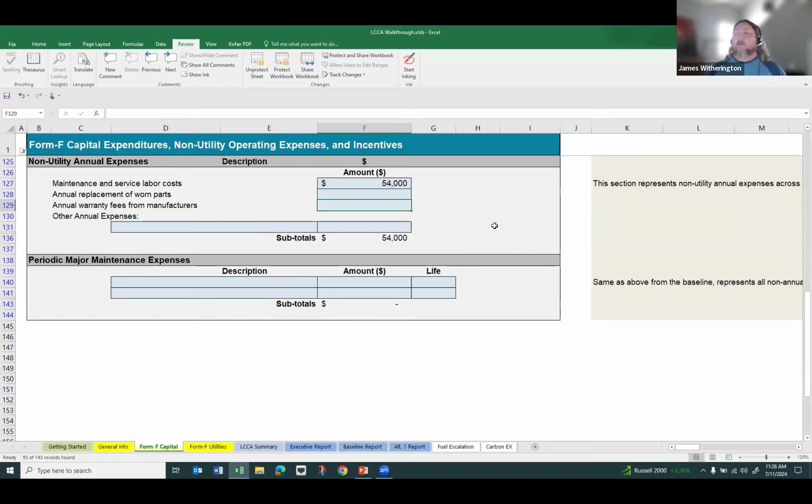What we're actually looking at here is the actual useful life on the ground. If you've been well maintaining that equipment, let's say the standard is 15 years and you're on year 25 and it's still running fine, then it's not technically beyond its useful life. In terms of determining what that remaining existing useful life is, that is definitely an engineering judgment piece that has to take place during the audit analysis. I hope I answered that correctly. Let me know if there's any follow-up on that.